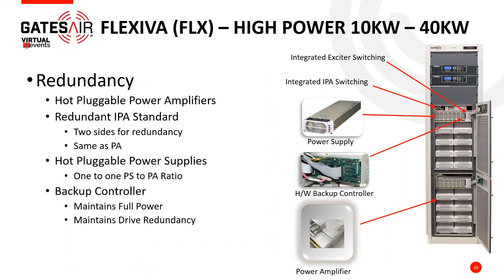This gives you an idea—very much the same look and feel as far as one-to-one redundancy in the power supplies and PAs. The power supplies are the same ones we use in the air-cooled units, and it has the same controller and redundancy within it. But at the bottom right of the screen, you can see the amplifier itself—a different amplifier with a cold plate on it, with liquid cooled connections and valves to support the liquid cooling through the system.